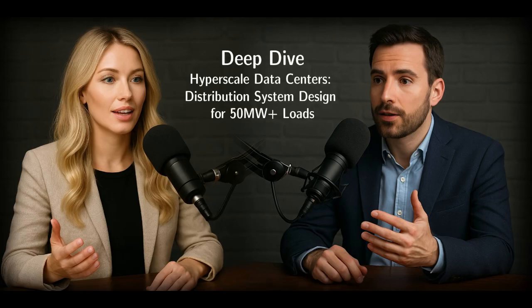Okay, let's take an example. Say a 35 megawatt data center at 25 kilovolt. What does that look like? Okay, 35 megawatts at 25 kilovolt, again assuming 0.95 power factor, draws about 850 ampere. Still substantial, but manageable. You could probably handle that with a 477 kcmil aluminum conductor. And voltage drop? Much better. Over 10 miles, you might only see about 1.8% drop. And you'd need more sophisticated protection than standard distribution, likely with communication assistance, but it's well-established technology.